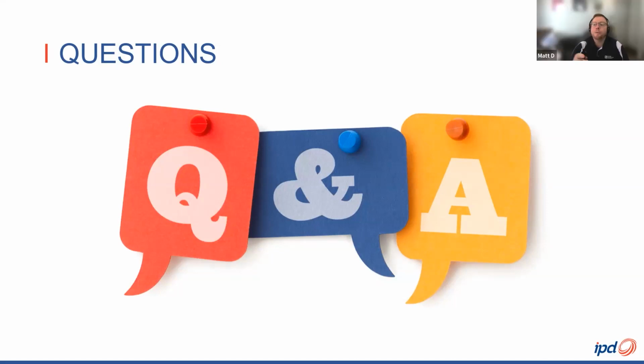No problems. We do have one final question. Let's make this the last one from Jason. Just wanted to clear up something you've been told. A theoretical situation: a voltage rise between the neutral and a functional earth. Would that trip the mechanism? It shouldn't, no, the voltage rise between the functional earth and the neutral. Neutral, yeah. It shouldn't. An RCD by its nature is doing a comparison of the load currents going out and coming back.